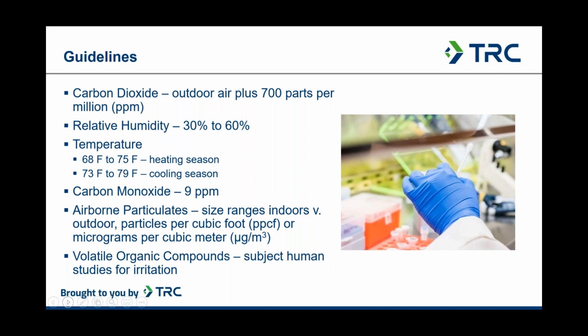Regarding airborne particulates, you can measure size ranges, indoors versus outdoors, in particles per cubic foot for relative filtration effectiveness evaluation. And another method is to measure how much mass of a particulate is present per volume of air. And that unit is called micrograms per meter cubed of air. Regarding the volatile organic compound measurement, that evaluation is based on subjective human studies where individuals report the presence of irritation effects or headaches at various VOC concentrations. And then there's a guideline on a no effect level. If it's below that, you don't expect the occupants to have a concern or complaint regarding the VOCs.